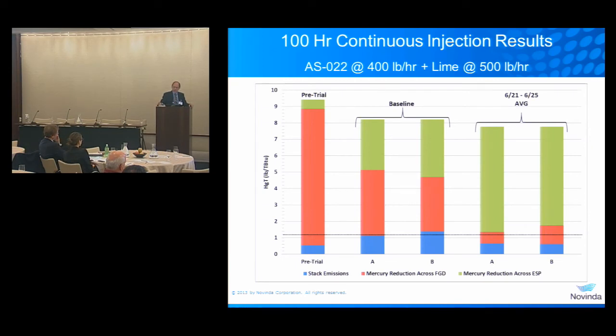So I think this reflects something that I know other investigators have talked about. I know specifically the guys at Southern Company have mentioned that often their wet FGD systems will, just with their capture of oxidized mercury, be able to meet MATS, but it's not 100%. It may be 60 or 70% of the time they can meet MATS. Things like load changes or coal changes can cause upsets that cause MATS exceedances at the stack, and so what they're looking for, and especially what the folks at Santee Cooper were looking for, was an active knob, something they can implement that will help them in those cases where they're not being able to meet MATS with their existing wet FGD. How can we actively inject a material that will get us to that MATS level and help us maintain compliance?